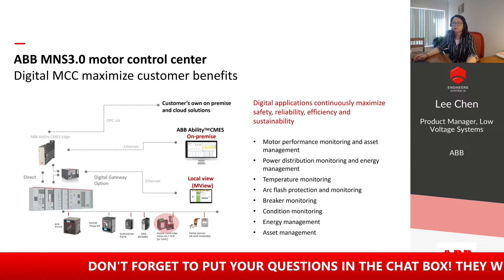Let's use two examples here to further elaborate how CMES improves efficiency. The first example, on the top, is the health index part of the dashboard a user sees when entering the CMES. If all is green, the user can close the window and continue with other important tasks. If a temperature problem, for example, is indicated through a color change, the user can then start assessing this by navigating to the second dashboard, a switchgear assembly or panel view that clearly indicates the location of the issue. This saves locating time and improves operational efficiency.